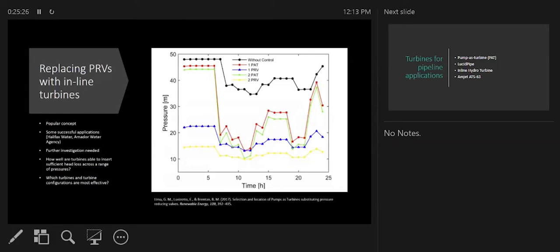There's at least one paper that looks into this, and they found that at low customer demands, the turbine alone was not able to impose sufficient head loss. So some sort of solution, whether it's putting a turbine in parallel with a PRV or some other kind of solution, has to address this failing at low consumer demands.